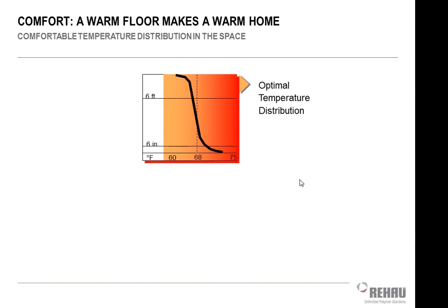So this gives you an idea, and some of you are probably familiar with ASHRAE Standard 55, which is the thermal comfort standard that we use in our industry that dictates the temperature distribution you can have vertically throughout a space. And that's why you see on here 6 inches and 6 feet on this chart. Basically, that ASHRAE standard dictates that between 6 inches off the floor and the occupied zone, which for a standing occupancy would be 6 feet, for a sitting occupancy like a desk or something like that would be 3.5 feet, in that range you're not supposed to have more than 5 degrees temperature stratification difference.